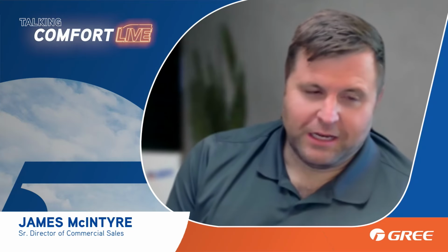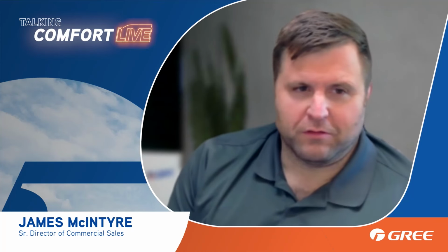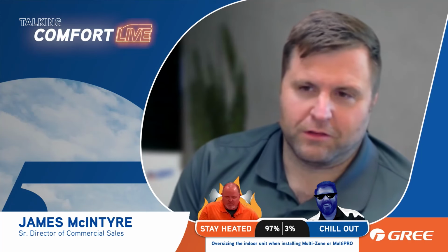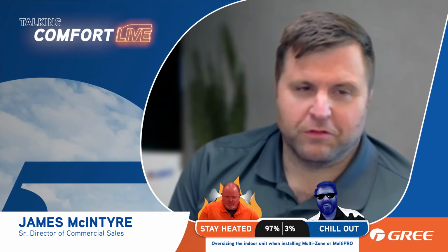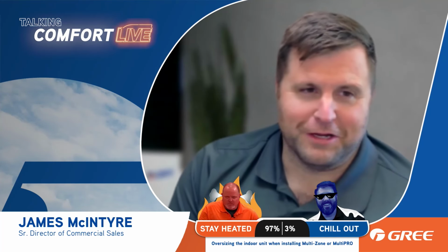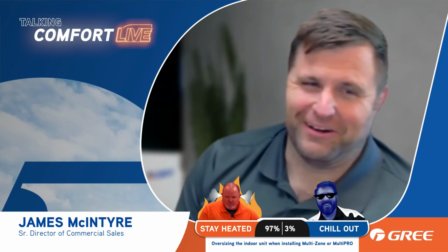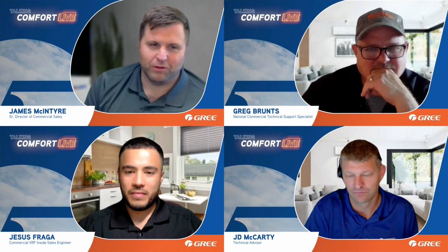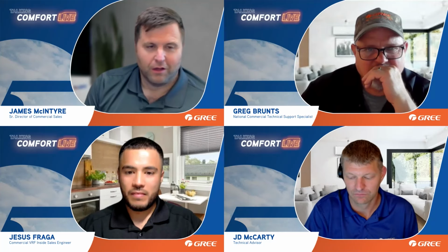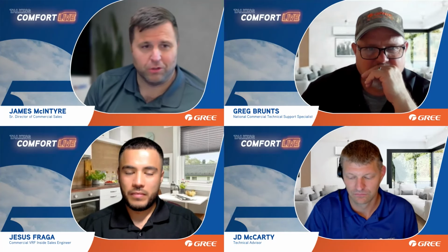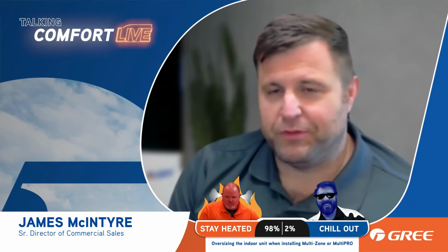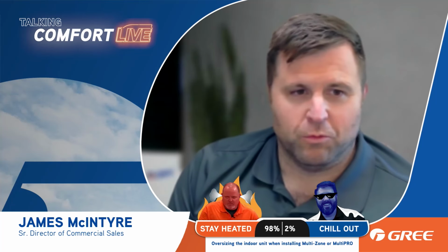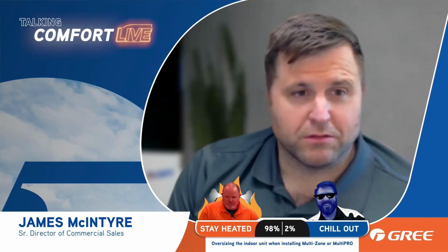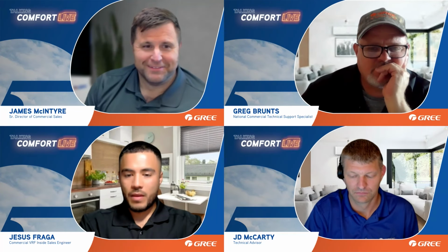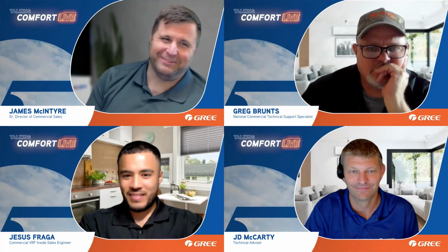I can give one example. We got a heat load calculation one time on a second story, and the calculation showed the floor was losing heat like it was a single story. Obviously that's not how second stories work — that's typically a heat gain, right? Which was enough to throw it off right there. And then we had 1-ton units in 110 square foot rooms, that kind of thing. The complaints were the complaints: it's overshooting, it's not accurate, it's not this, it's not that. You'd probably have an argument if that was the one unit we sold that year, but we sell a lot of them. I've got them in my house — I know one of them's oversized. I'm not saying I did it right, I'm just saying I've got it in my house.